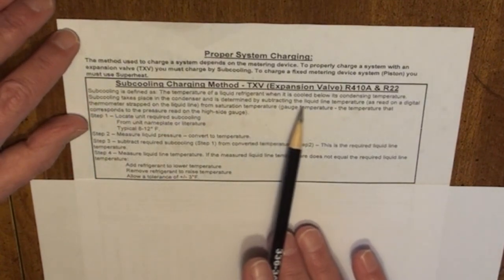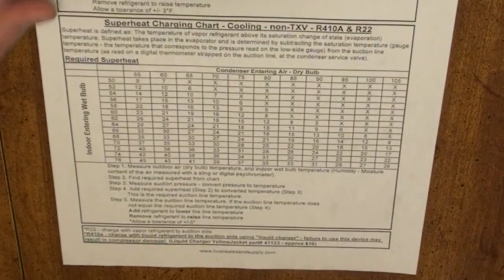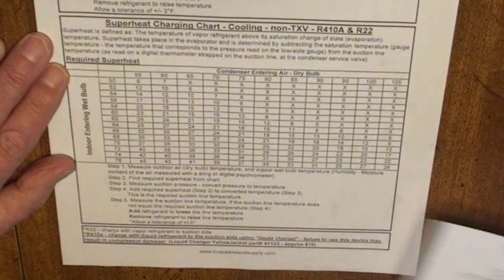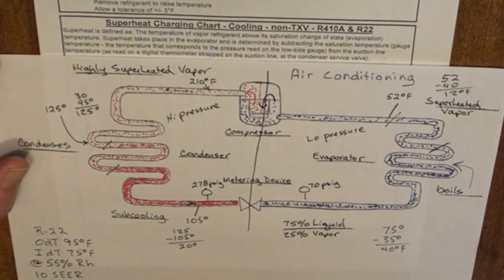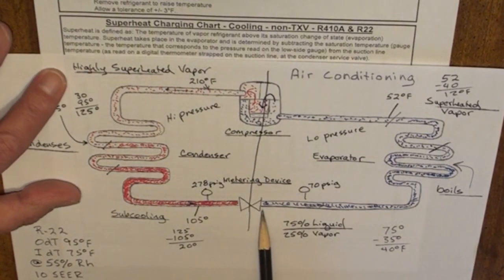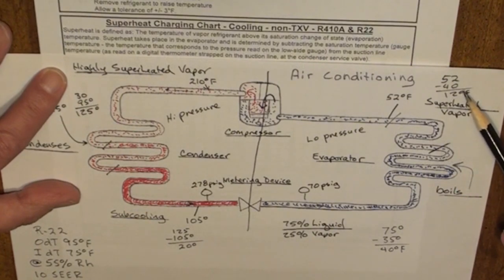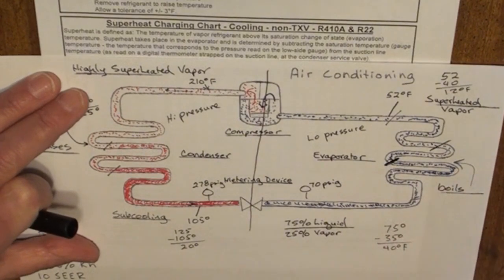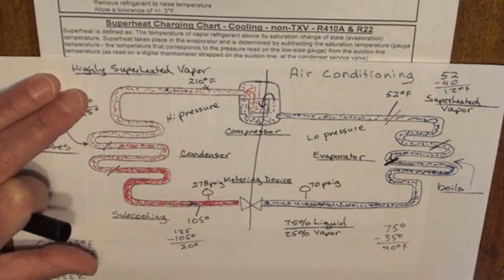Again, this subcooling method is for TXV expansion valves. The second chart is a little more complicated — this is the superheat charging chart for non-TXV 410A and R22 systems. With a fixed orifice system, high-side pressures dictate how much refrigerant is fed to the evaporator. If we have a high superheat, that means the refrigerant boiled to a pure vapor much earlier in the system than expected, so it takes on sensible heat through a larger section of the evaporator.